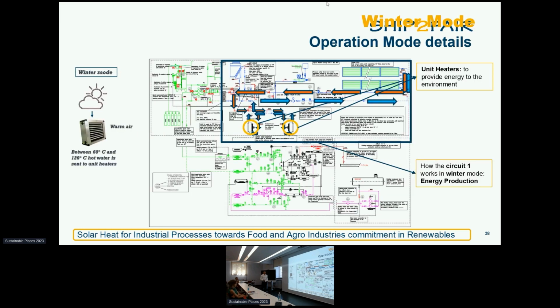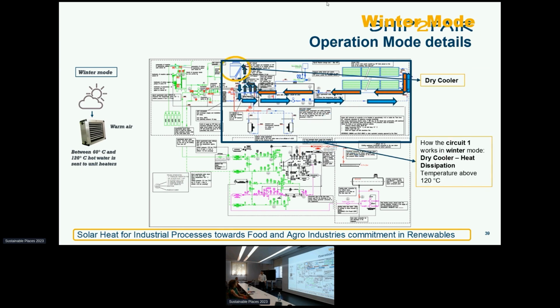Going back to the P&ID, this is how circuit 1 works during the winter mode. As you can see, we have in red the hot water exiting the solar panels, fueling the 2 unit heaters that provide heat to the environment, and then coming back to the solar panels. This happens when circuit 1's temperature is between 60 and 120 degrees. But when the temperature increases above 120 degrees, the flow is driven to the dry cooler to dissipate this excess of energy. This happens during the winter mode.